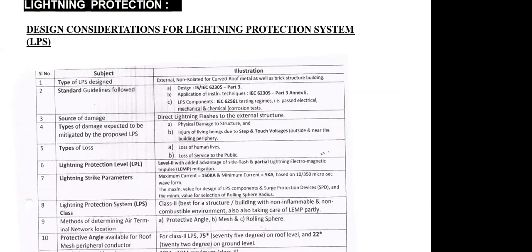lightning protection currents. So what is the type of LPS design? It is external, non-isolated, for curved metal as well as brick structure buildings. The standard guideline is IEC 62305, and the source of damage is direct lightning flashes to the external structure. We know that when lightning happens, it hits the building itself. Types of damage expected to be mitigated by the proposed LPS: physical damage to the structure, and injury to living beings due to step and touch voltage outside and near the building periphery. This is what we discussed.